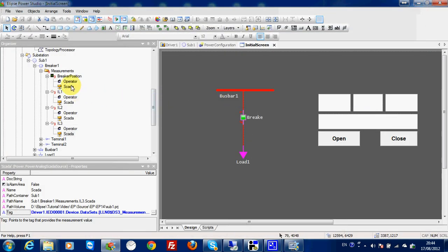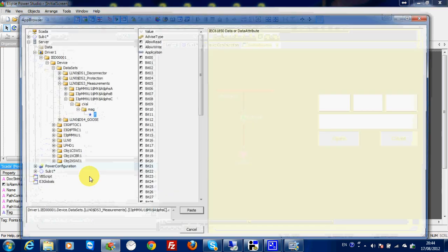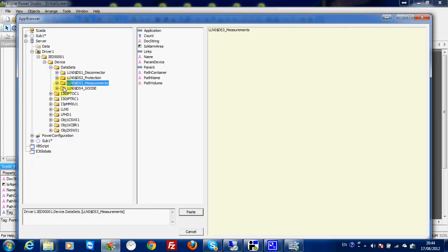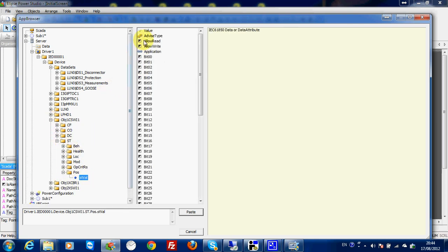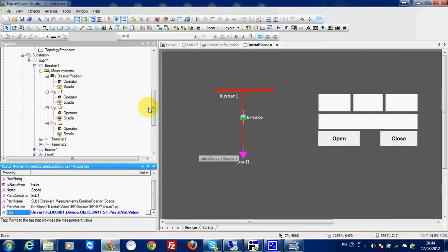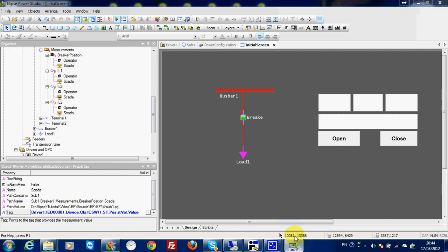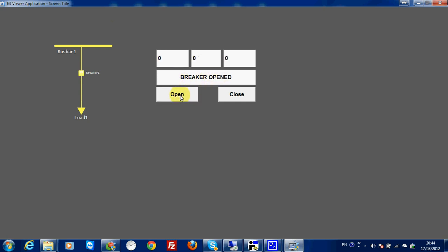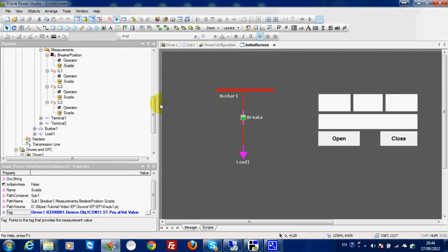Right now, what I need to do is show the breaker position. The breaker position here — I need to choose the tag, and this tag I can choose from inside my dataset or from the object ST position value. I need to be careful about the value of the open and closed state. So if I go back to the project here, breaker is closed, then breaker is open. I need to check carefully why it doesn't do anything.